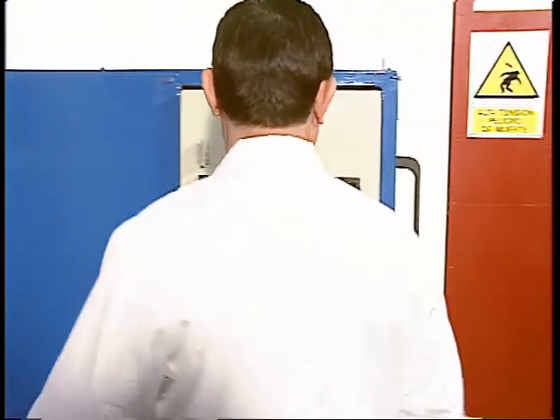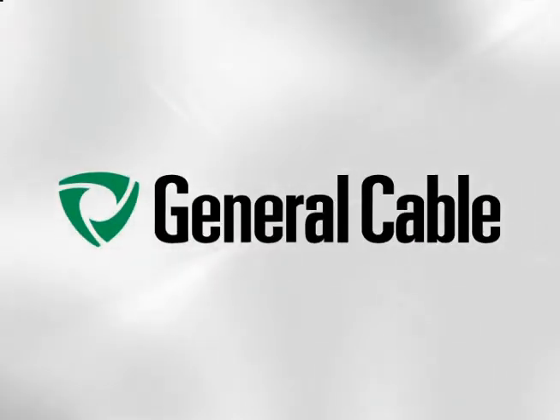After 90 minutes, the cable is still serviceable, with no crossing or breaks in the leads, and it still carries the 1 kilovolt voltage with no fall-off. The excellent results of these tests are factors of vital importance for the rapid intervention of the fire prevention and evacuation services. General Cable, committed to the safety of people and equipment in electrical installations, is aware that immediate evacuation depends on the quality of its high-security cables.